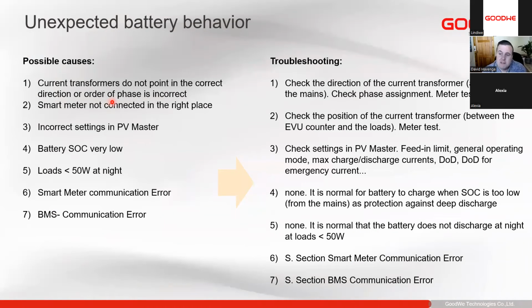So first thing can be our CTs are incorrect. So if the CTs of the smart meter are incorrect, that will also result in strange battery behavior, or the smart meter may not be connected in the correct place. So that does sometimes happen as well. We're not actually reading all the utility. We are reading just the loads, and when the inverter feeds to the loads, then it sees it as export, and then it starts to charge the batteries again. So we need to make sure that smart meter CTs are in the correct place.